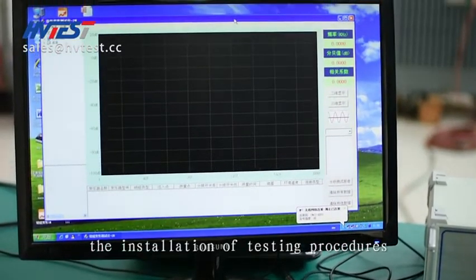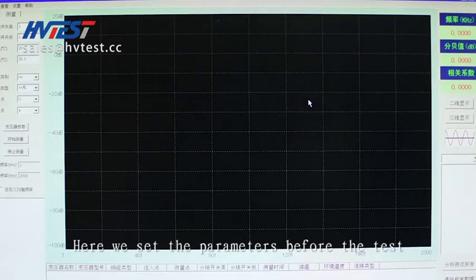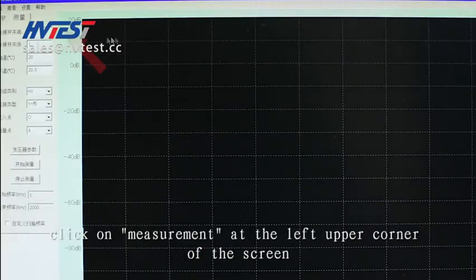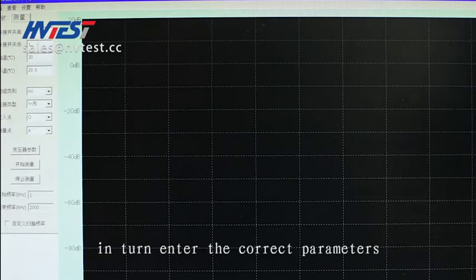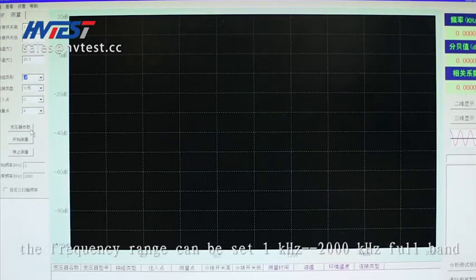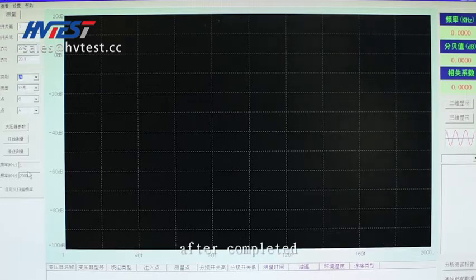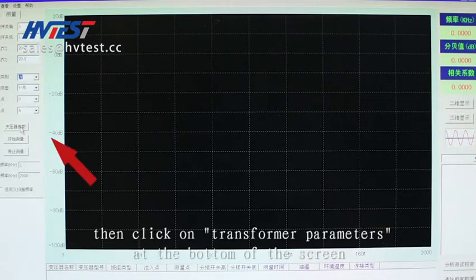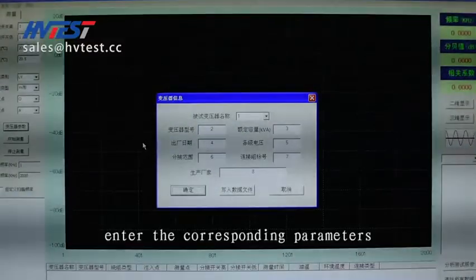Enter the winding deformation test procedures. Here we set the parameters before the test. Click on measurement at the upper left corner of the screen. According to the actual situation, enter the correct parameters in turn. When performing the test, the frequency range can be set from 1 kHz to 2000 kHz full band. After completed, click on transformer parameters at the bottom of the screen and enter the corresponding parameters according to the transformer nameplate.